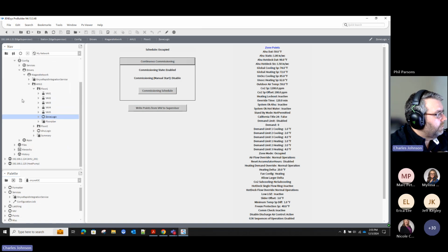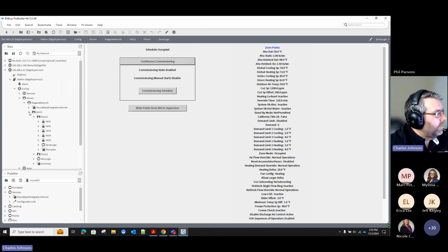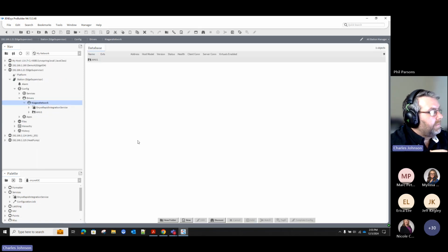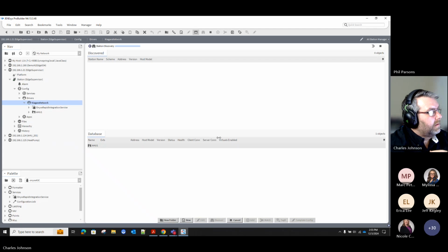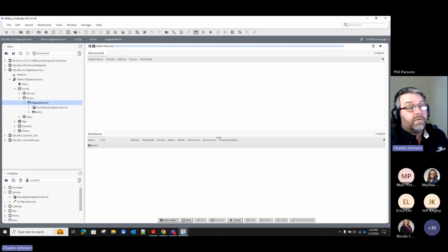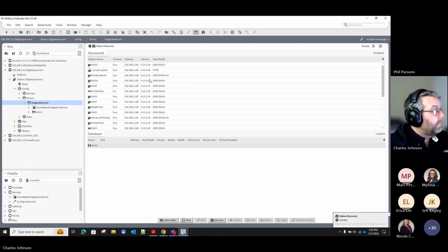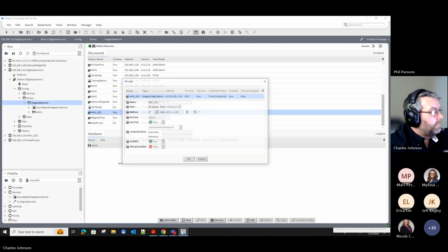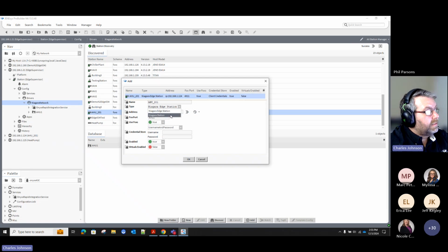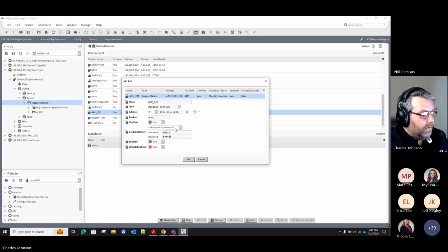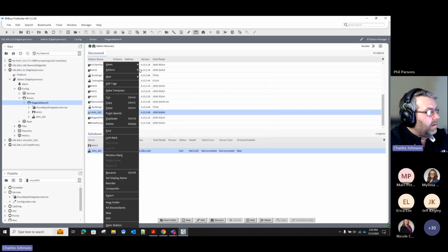The last thing I'll show you is, if you wanted to bring in your air handler, simply go to your Niagara network, select Discover as long as you have the ability to discover on your Niagara network, find your air handler, choose whether or not it's a Niagara or Niagara Edge station, and go ahead and hit ping.